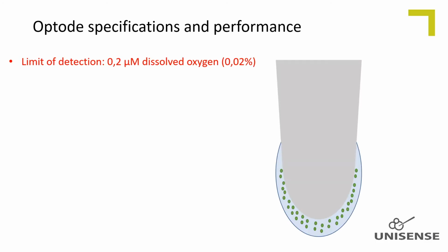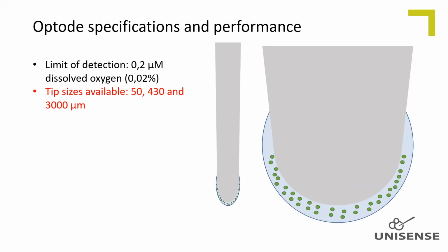I will now turn to the actual performance and specs of the oxygen optodes. Recall that these specs are only guaranteed with use of a Unisense optode meter. The limit of detection is validated to be about 0.2 micromolar dissolved oxygen. This equals approximately the concentration in water in equilibrium with 0.02% oxygen. We sell glass fiber-based optodes with 50 and 430 micrometer tip.